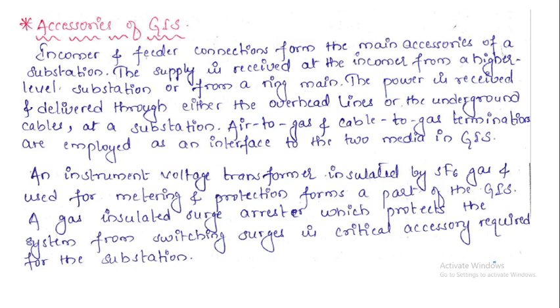Either we can have an air to gas or a gas to cable to gas. So these are the terminations which we will be using in case of an interface between the two media in the GIS system. An instrument voltage transformer insulated by SF6 gas and used for metering and protection forms a part of the GIS. A gas insulated surge arrestor which protects the system from switching surges is a critical accessory required for the substation.